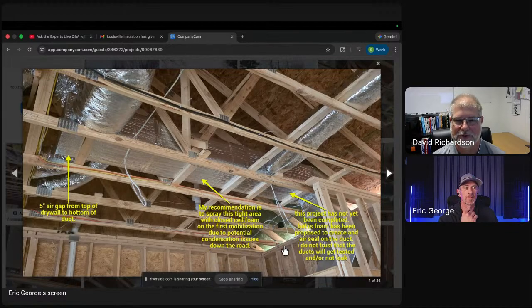Bubble wrap has what is called, there are two different types of R values with duct insulation. With any type of insulation, you have a rated R value and an effective R value. With bubble wrap, there's a rated R value, but the effective R value tends to be much lower unless all the installation details are hit just perfectly. One of those depends on a dead airspace, with spacers in between underneath that insulation before it's applied. Many times those spacers are not installed. It's just applied directly to the metal, so that dead airspace is non-existent. The other thing is the ducts would have to be 100% airtight, because if there's any leakage underneath that insulation, it'll act as a secondary duct, and the air will just move back and forth. That creates what's called a convective loop, and it transfers heat to the opposite side of the insulation against the ducts, and that's where the condensation will start to set up.